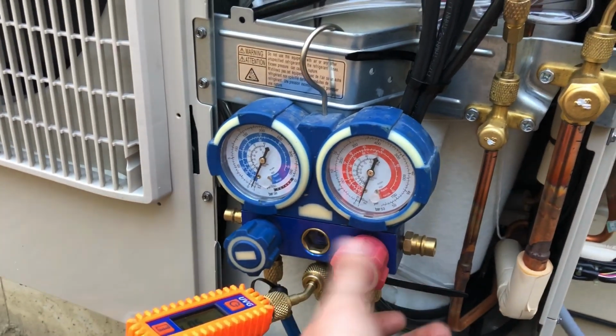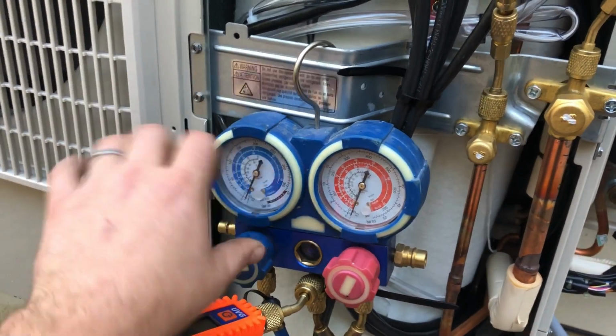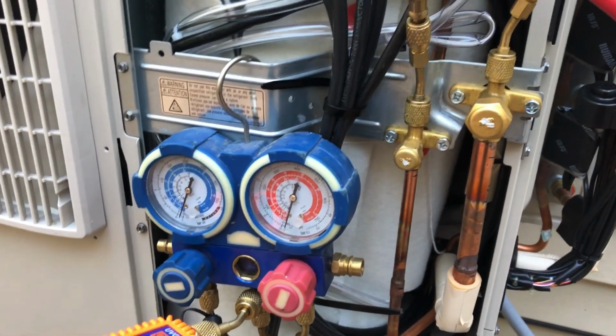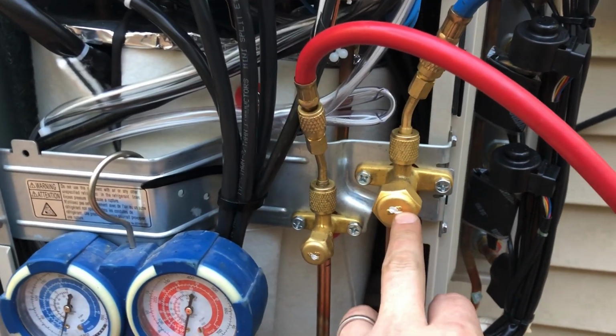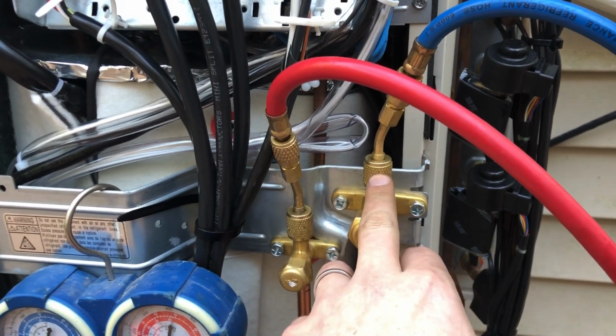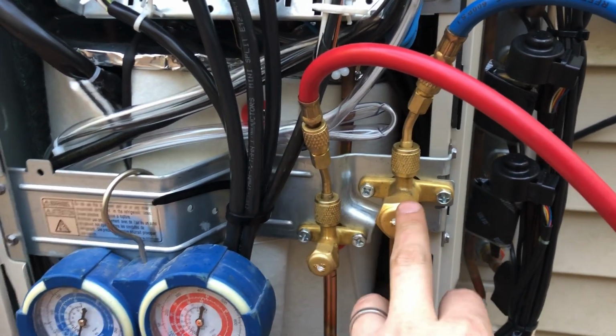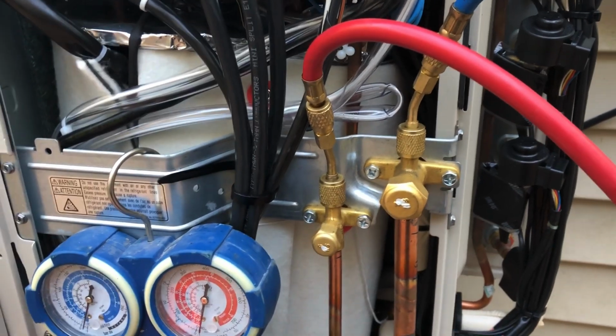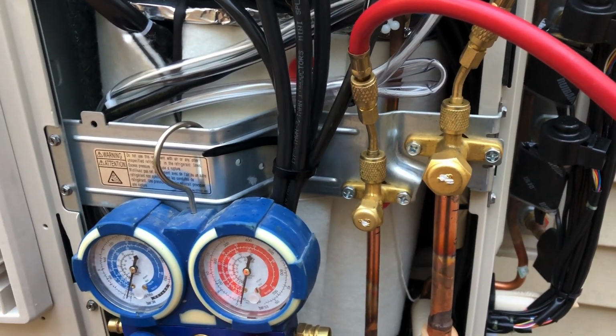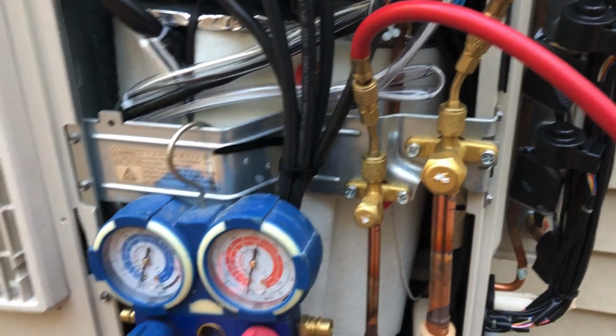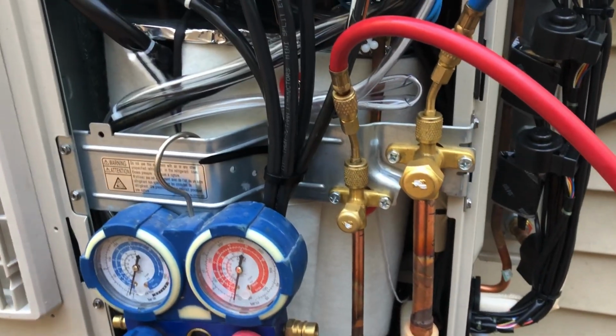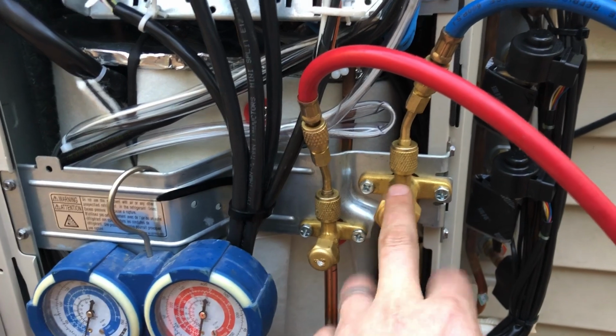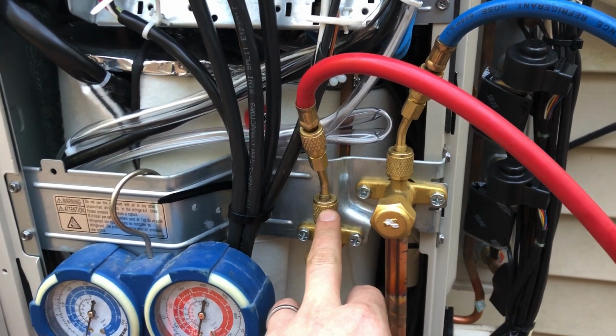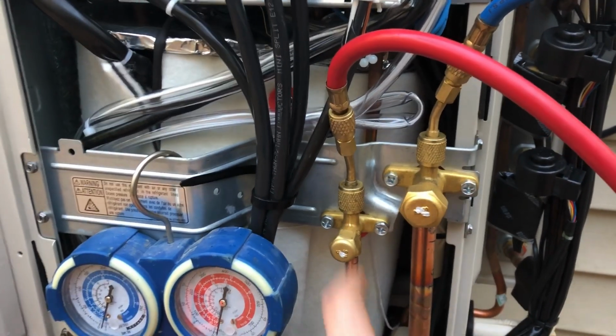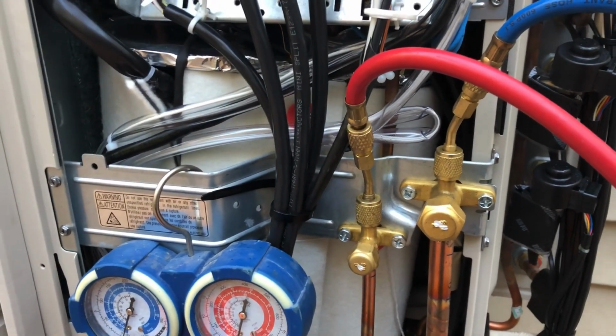So again, turn the valves off when you're ready. When you're done vacuuming, turn them off. Then you can turn your vacuum pump off, and then you open these valves and then break these. If you break these first before you open the valves, then you just let air back into your system, and so everything that you just did was wasted. So again, turn the valves off, turn the pump off, open the valves, you'll hear the refrigerant come through, and then you're going to disconnect these. A small amount of HVAC refrigerant will come out. That's fine.